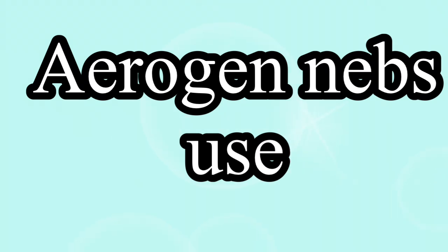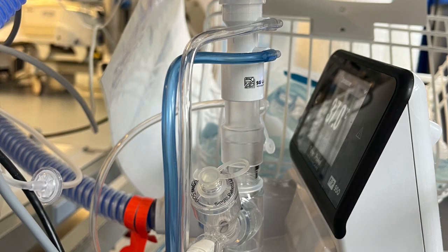Nebulizing medications within the ventilation circuit during inhaled nitric oxide therapy risks clogging the filter in the water trap and triggering the high priority alarm patient sample line blocked. It can also cause unreliable NO, NO2, O2 patient monitoring values. If it is used, the manufacturer recommends a filter being used, which can be placed at the water trap. On discussion with a consultant body, it has been deemed safer to avoid the use of Aerogen nebulization when patients are on nitric oxide therapy.